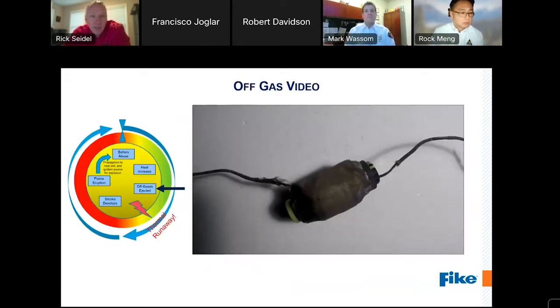Judy, if you can please click on the video to see what an off-gas event looks like. And I'd ask everyone to focus on the upper right-hand side of the battery. I think it may have just went and we kind of missed it. If you can try to replay it there for us, look at the upper right of the battery. You see the battery jump just a little bit and some sparkles or sparks pop off the upper top right corner of the battery there. Those were the off gases being ejected from the casing of this lithium-ion, just AA size battery wrapped in heat trace, heated up to a point of failure to where that vent pops and ejects the off gases from the battery. That's the amount and trace amount of gases that could typically be ejected from a battery that the Lion Tamer system can pick up when properly calibrated and strategically located in the airflow of the battery.